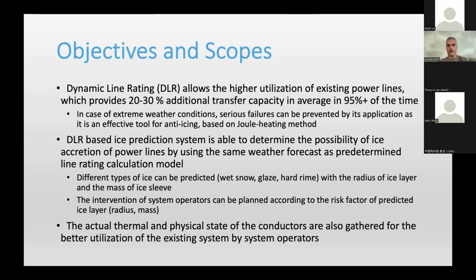And there is also what we call anti-icing prevention, which means using the Joule heating of the conductor itself. By giving a higher power to the conductor, we can preheat the conductor itself, using also the same sensoring technology.